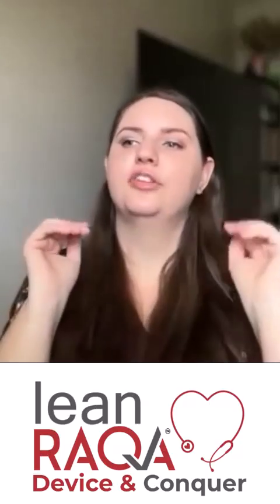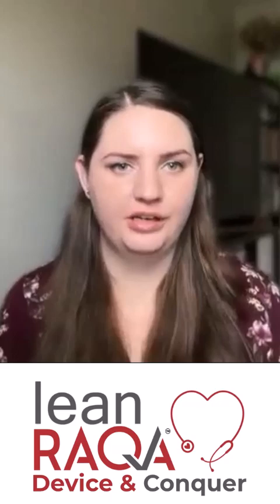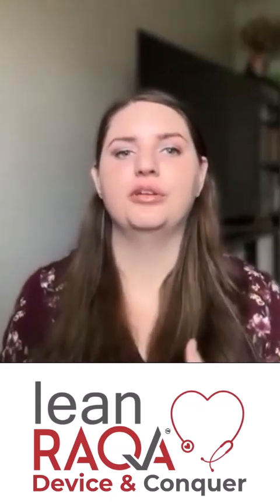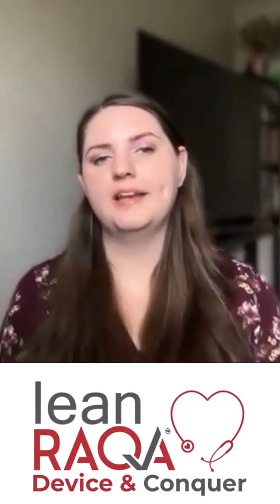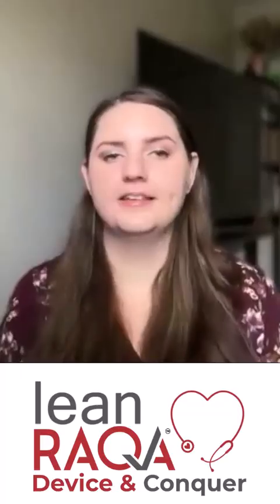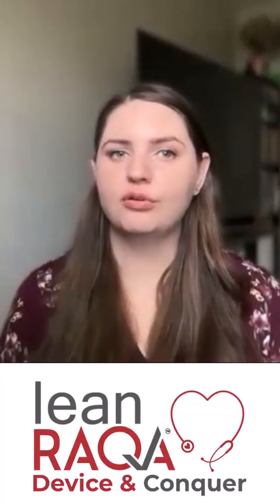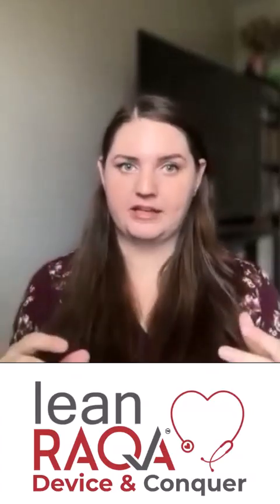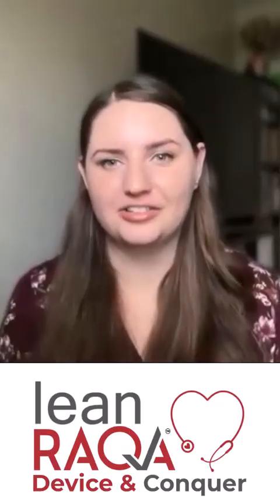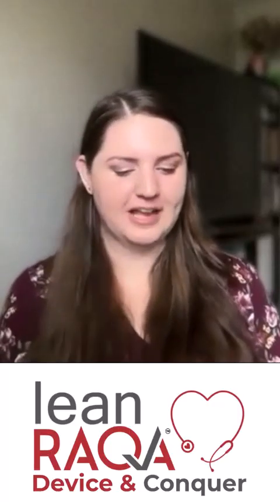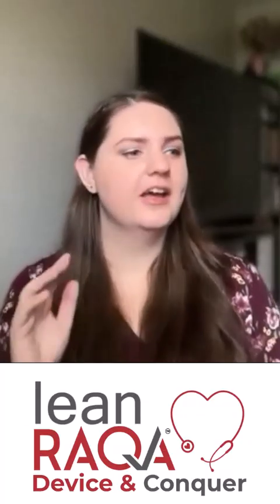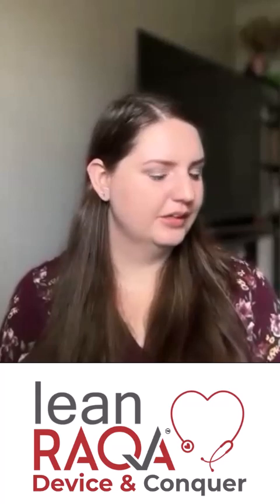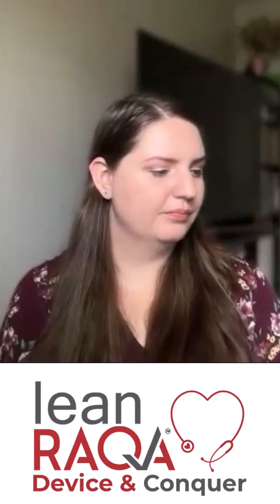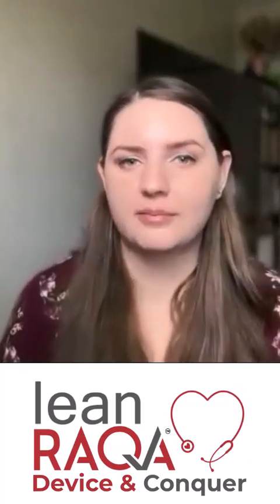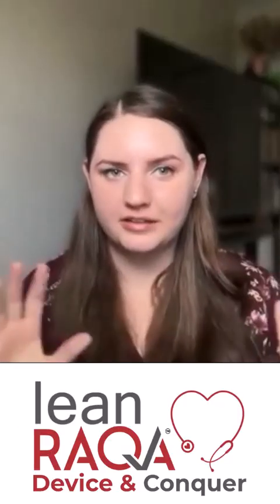So you determine the class of your product, class one, two, or three. That's kind of a starting point. But the product code is really where you get the meat of your requirements. Depending on your product code, it can tell you your consensus standards, it can tell you if you have special controls. It will guide you to the wording of your regulation, which we'll talk about a little bit later because regulations also deserve their own little section in this podcast. It tells you what your submission requirements are, and it can even tell you a lot of history on that product itself, by seeing what other products are in companion product codes under a regulation.